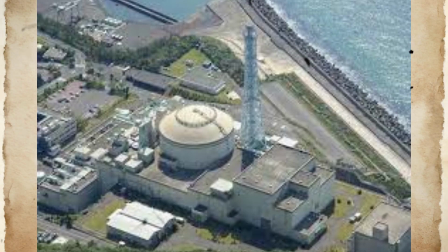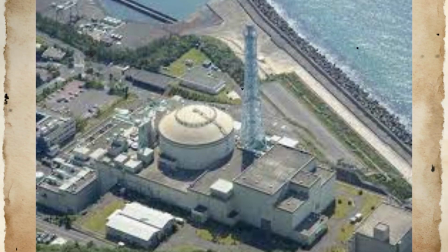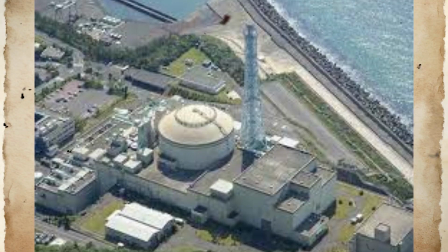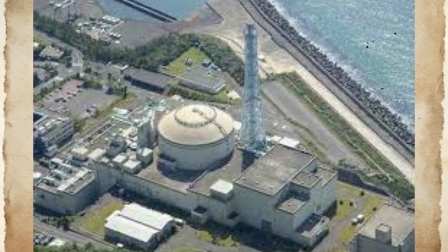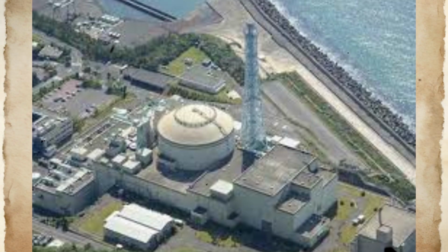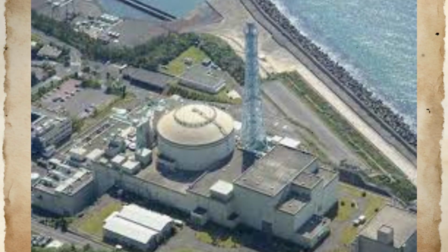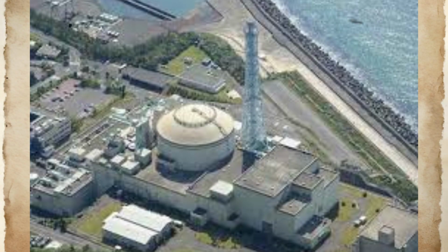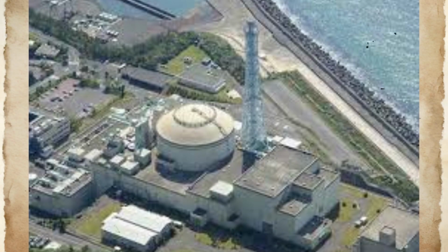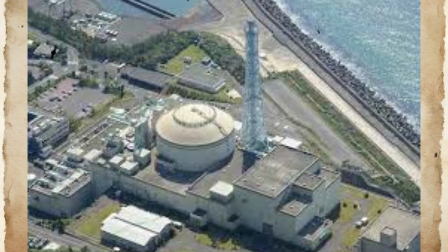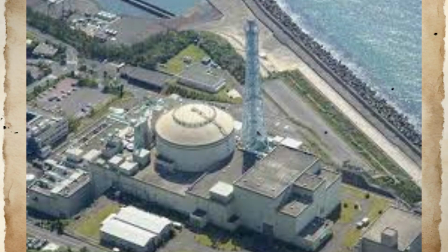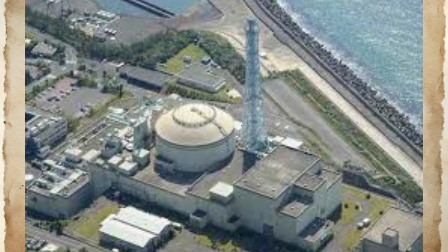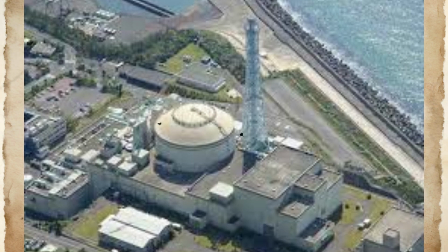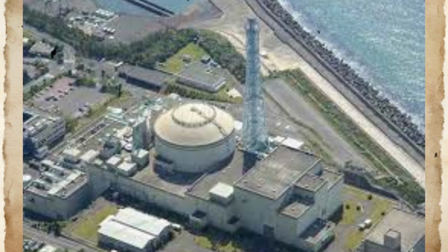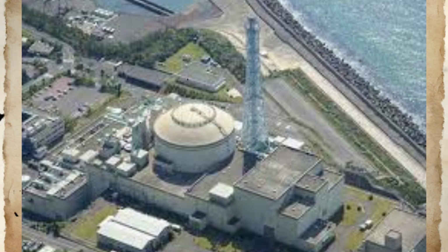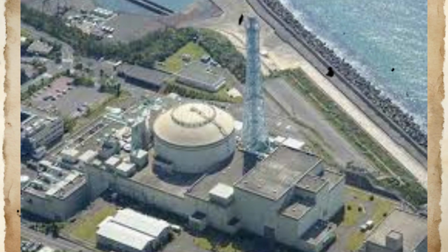The first inspection of the SGS Loop C piping room occurred at 2050, when operators partially opened the door to assess conditions inside the room. They observed an increase in white smoke compared to earlier observations, indicating that the reaction between escaped sodium and atmospheric air was continuing. This observation confirmed that sodium was continuing to leak from the system, and that the leak had not self-sealed. The visual confirmation of continuing sodium leakage prompted operators to implement more restrictive emergency procedures.